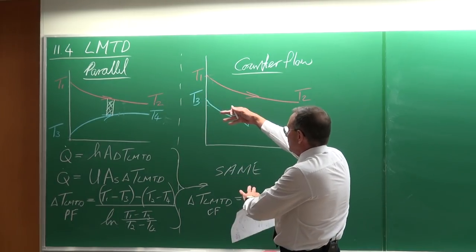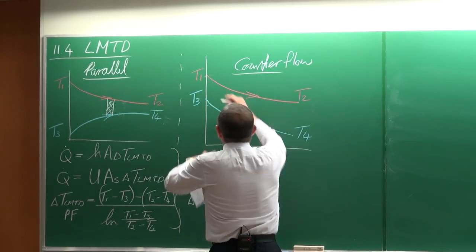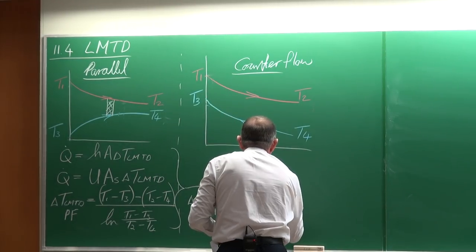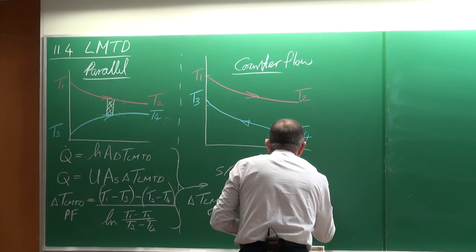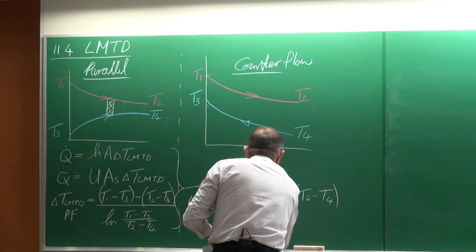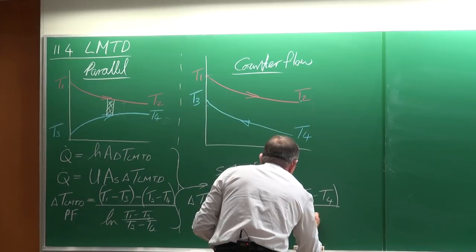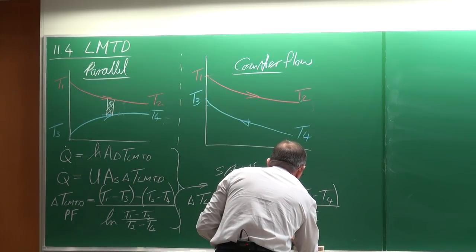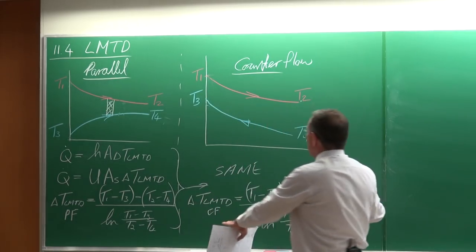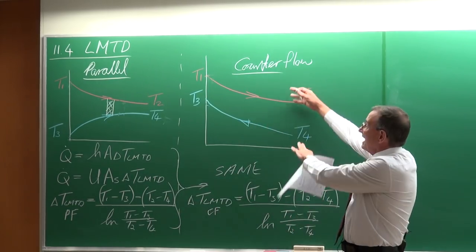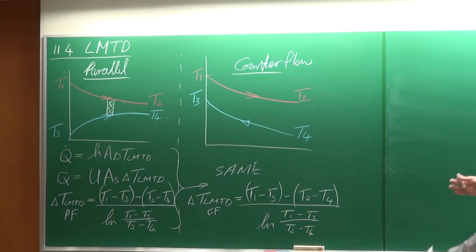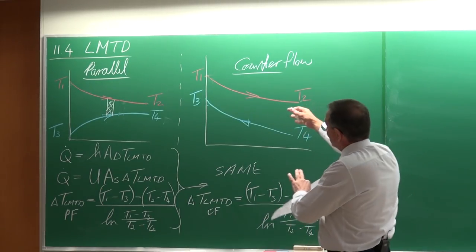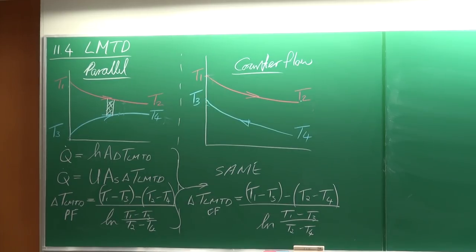Let's calculate the LMTD for counter flow. It is T1 minus T3, minus T2 minus T4, divided by the natural log of those two terms. So these two LMTDs are exactly the same expression, but it depends on the nomenclature you use. If you do the sketch, it is very simple to ensure you treat it correctly.